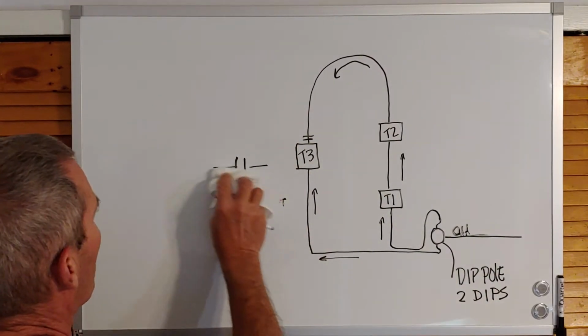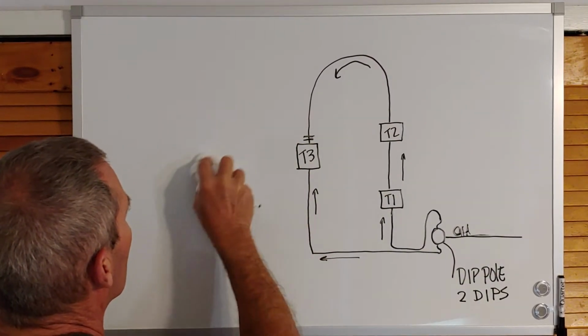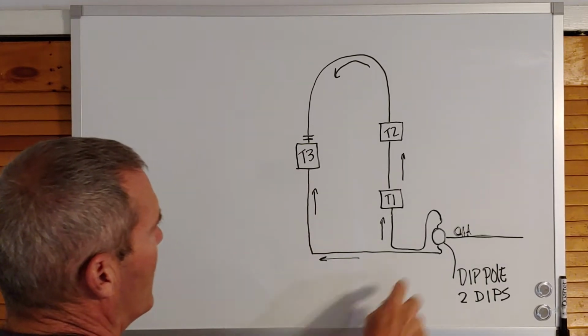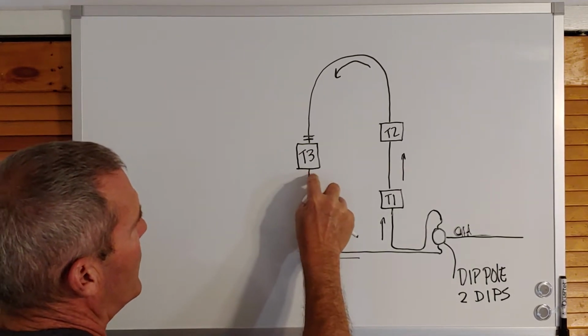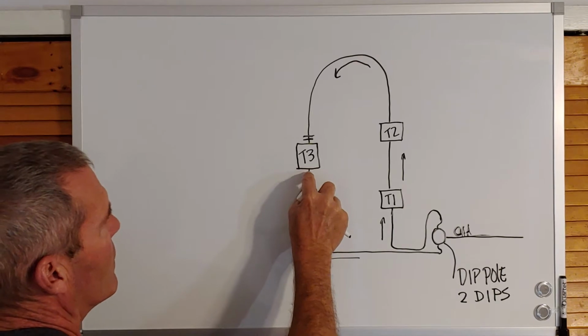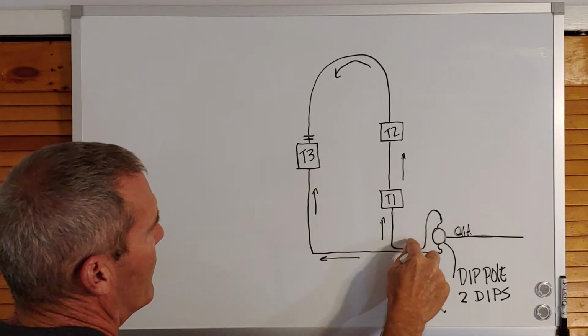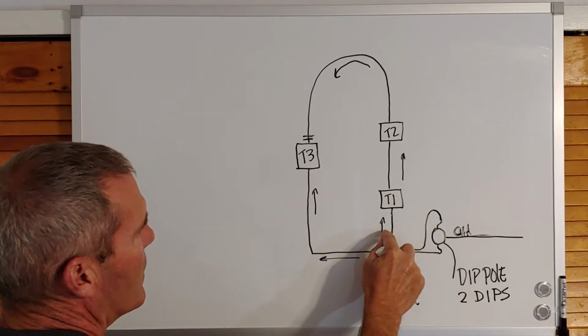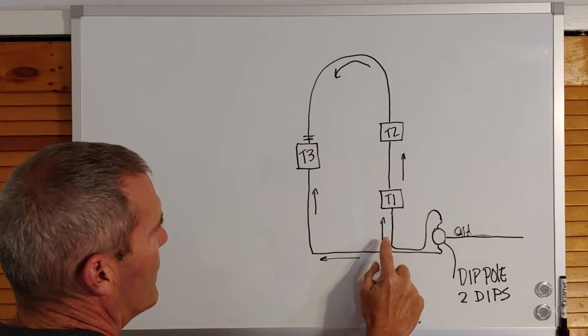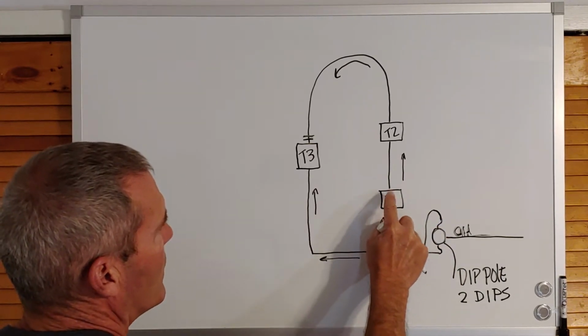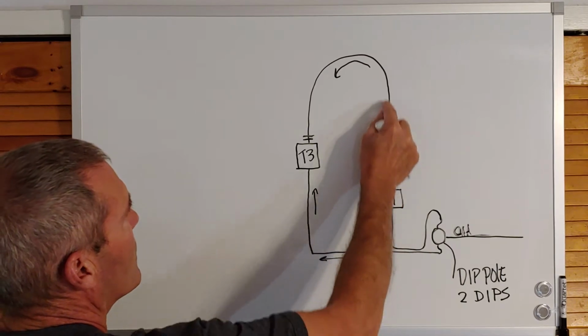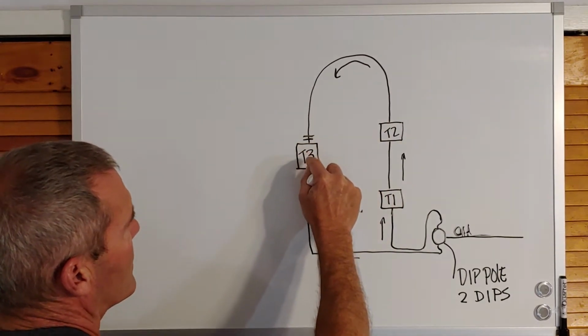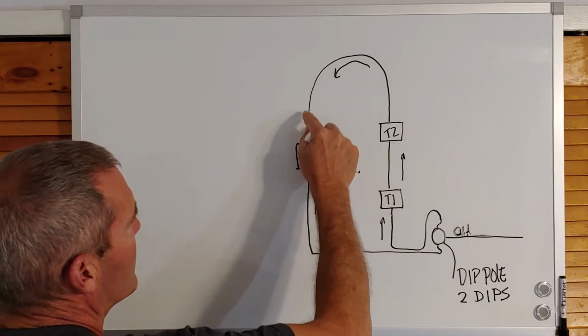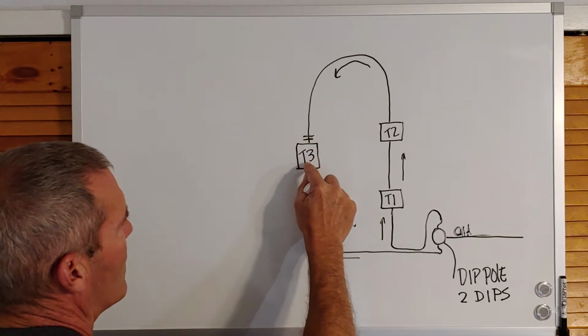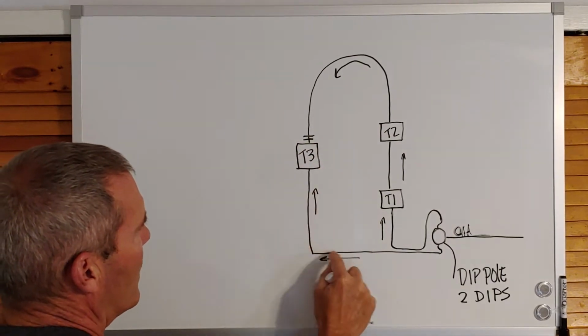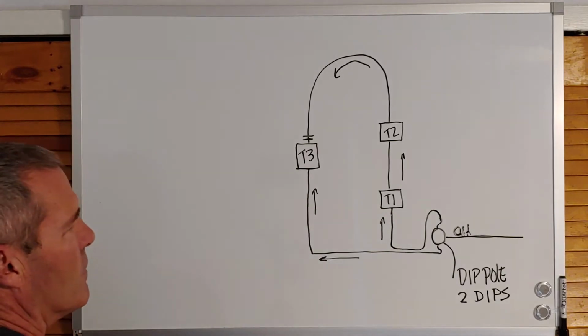It's also normal practice that our normal open point is not placed on this side of T3. If we fed all the way around - and this is my feed direction, watch the arrows - this dip came off and feeds this direction to T1, this direction to T2, around the back, and this direction to T3. If I fed the transformer inbound on A here, I would have no indication if this cable ever faulted.